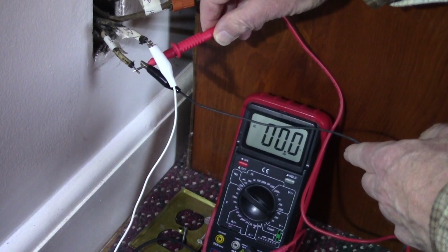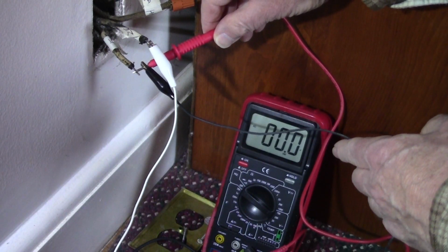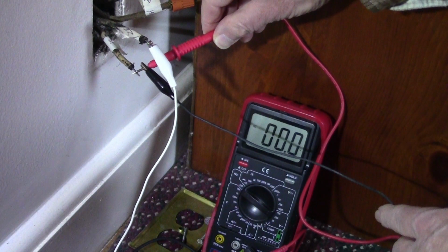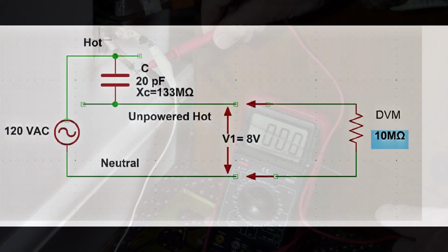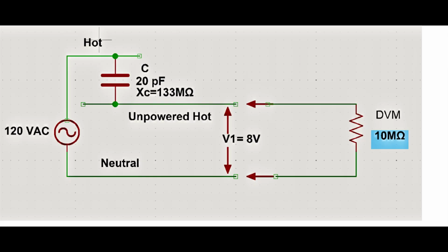The voltage drops so low that the DVM measures 0, and that proves that the cause of the phantom voltage is stray capacitance, and you know it is not the result of miswiring or some other fault. Just to recap, you are seeing the effect of an AC voltage divider caused by stray capacitance. The capacitive reactance is much larger than the input resistance of the DVM, resulting in a portion of the line voltage being present and measured at the DVM.